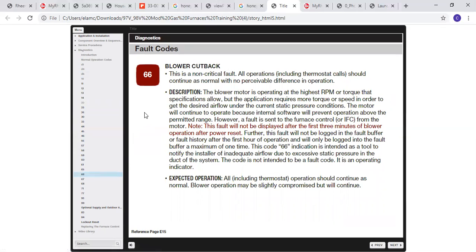Let's see here. 66. This is a big one. There again, we're dealing with an ECM motor. If you turn the furnace on and you're looking at your 7-segment display, you may very well get a 66 that comes on immediately. It's trying to tell you something. It says it's a non-critical fault. Everything will still work, but it's indicating that the furnace blower is operating at the highest RPM or torque that the specifications allow. So it's telling you about your static pressure, whether it's on your supply side or your return side.